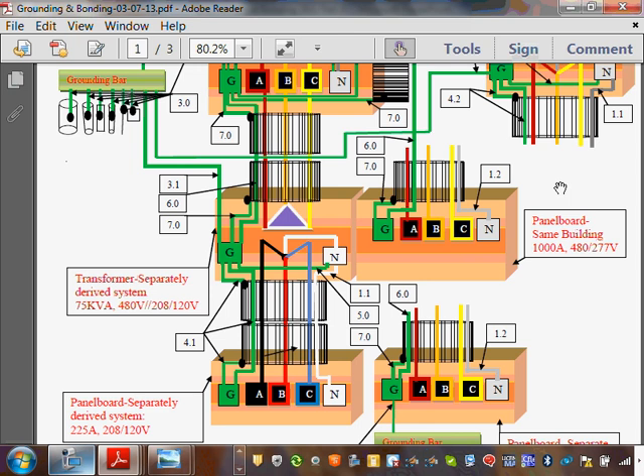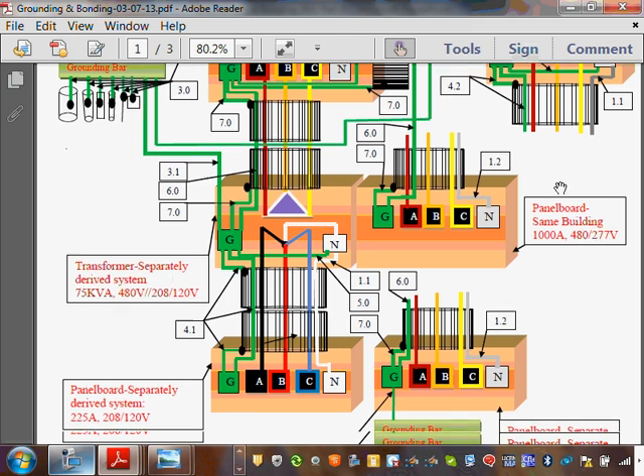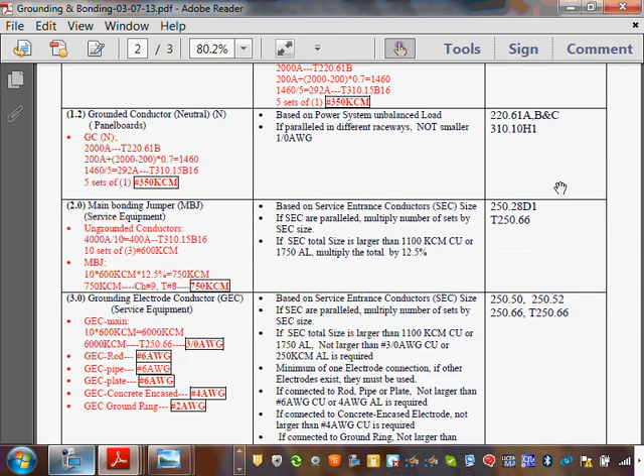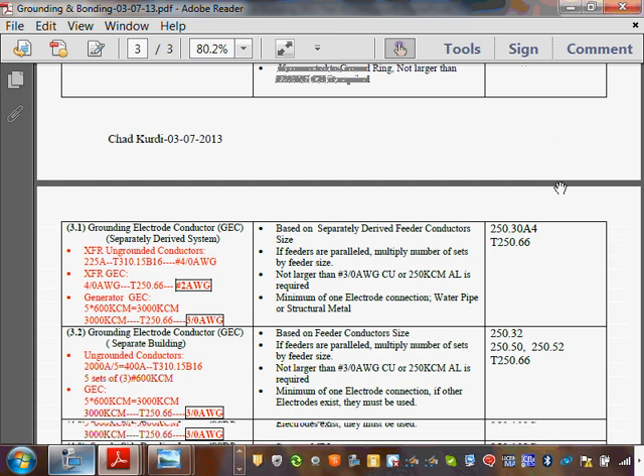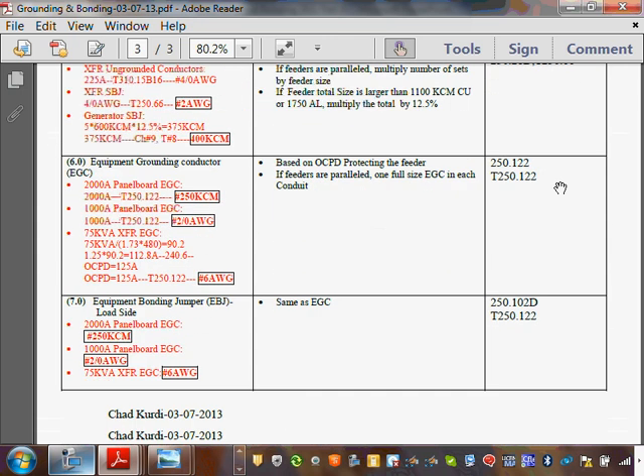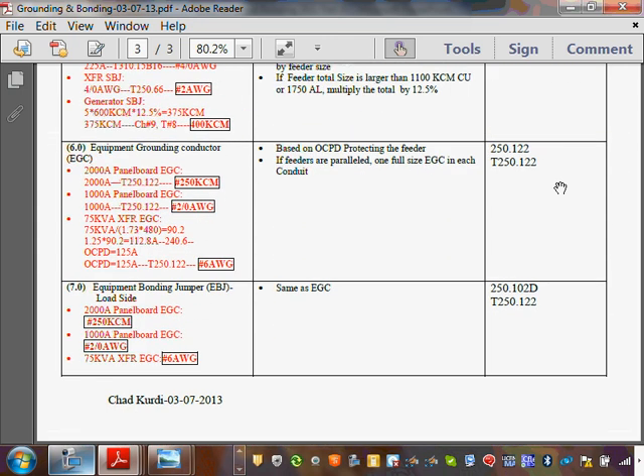Okay, so let's go 6.0 for the transformer. If you go to 6.0, it's the same thing for a transformer all the way. This is how we size that for a separately derived system. So, equipment grounding conductor, 6.0. That was for the 75 kVA transformer, right? That's my transformer size. You find the full load current of this transformer, assume it's continuous current, so you multiply by 1.25, and that's what you get, 112.8.